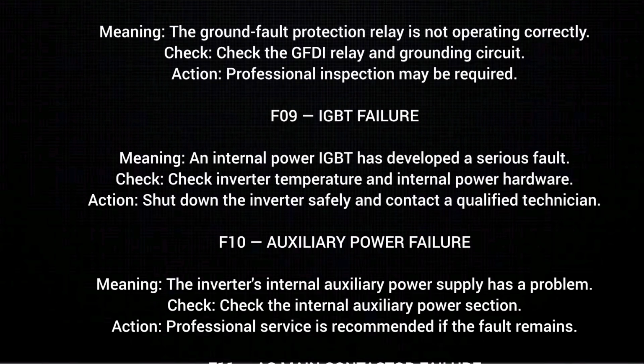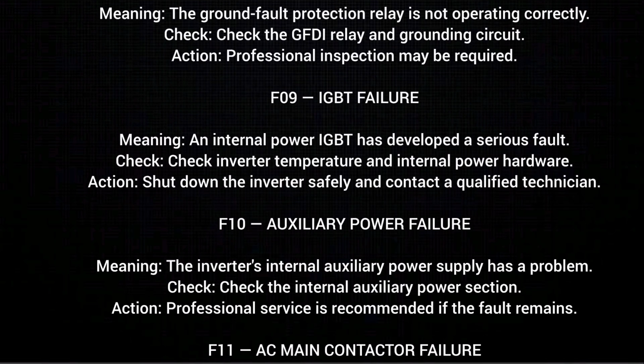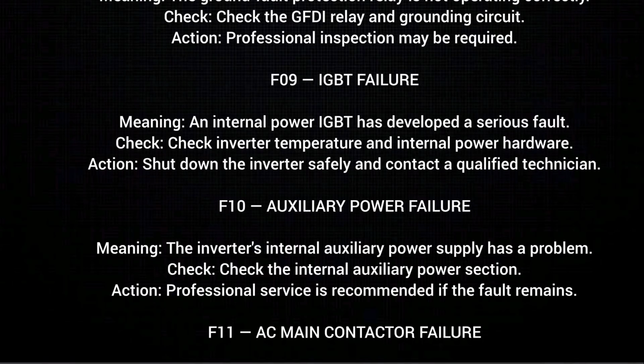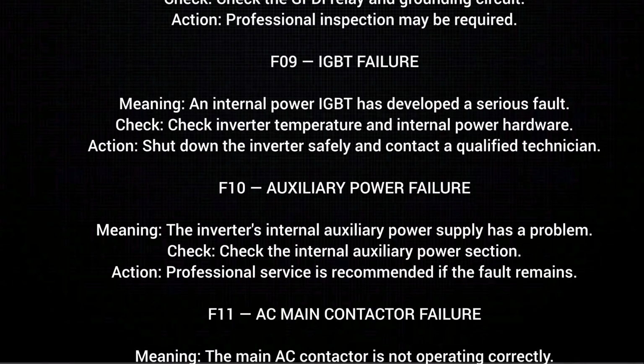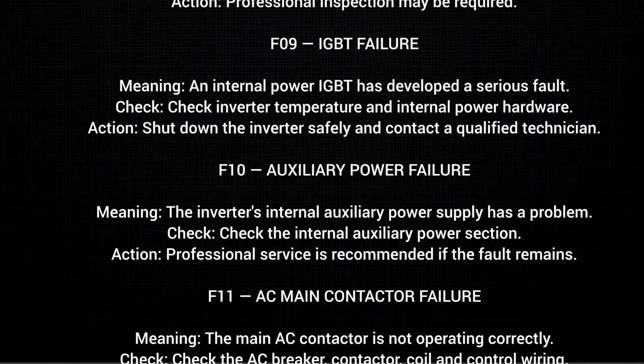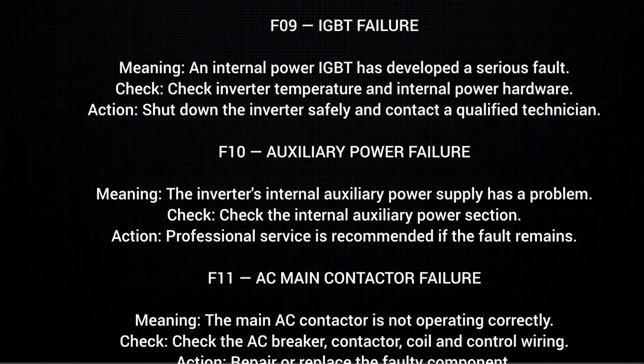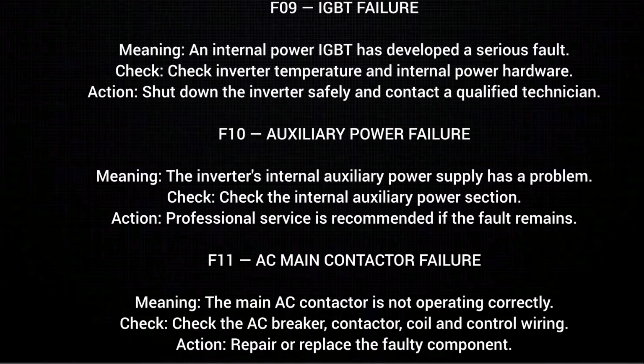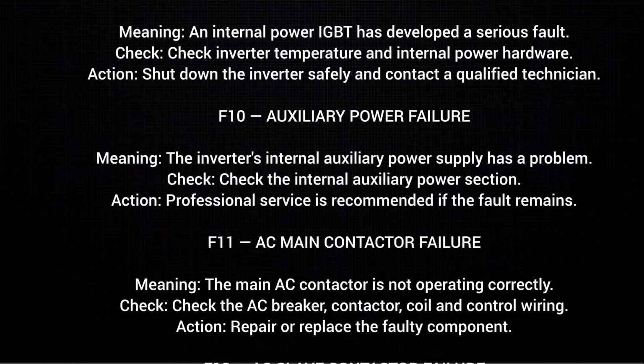F09 IGBT failure, meaning an internal power IGBT has developed a serious fault. Check. Check inverter temperature and internal power hardware. Action. Shut down the inverter safely and contact a qualified technician.